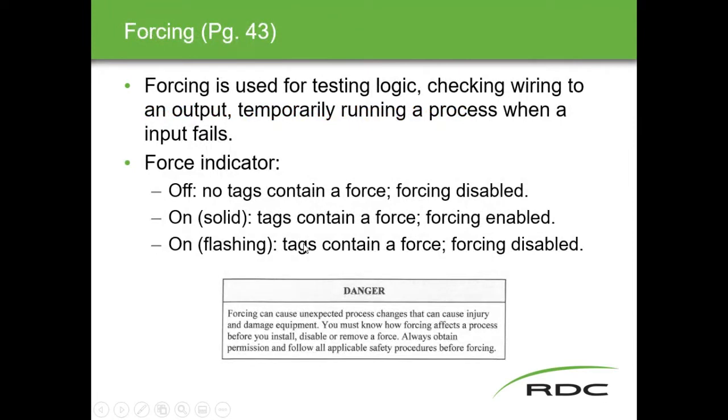Forcing is something that we haven't done, and I'll get you guys to do this in the next lab too, but forcing is a great tool for testing the logic or checking the wiring to an output or temporarily running a process when an input fails. Up in the top left-hand corner of the Logix 5000 software, and again, I'll show this to you in the lab, there is a force indicator that will let you know if there are any forces on or not. You can click on that and it'll tell you which tags or data points are forced, so that you know. Forcing is a great tool for startup and commissioning.